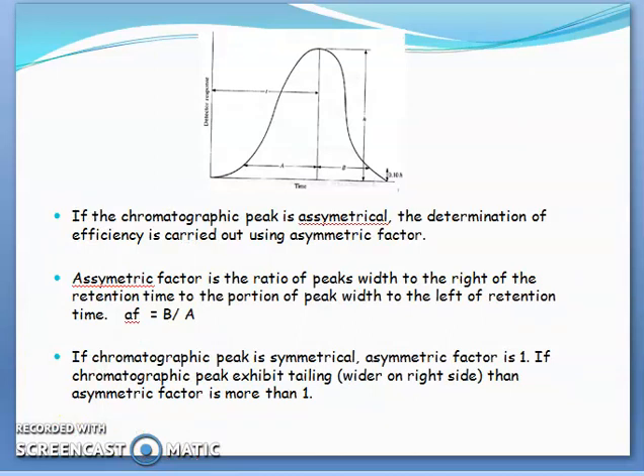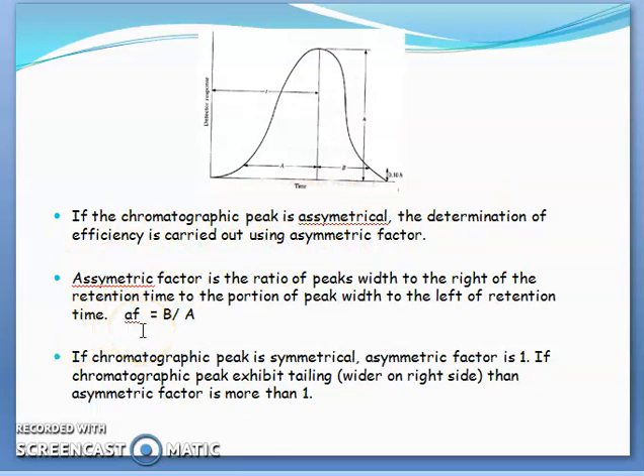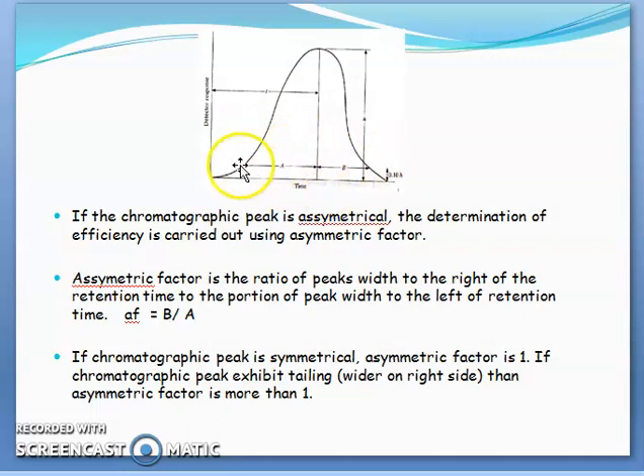For an asymmetric peak, the efficiency is determined using the asymmetric factor AF. The asymmetric factor AF equals B/A, which is the ratio of peak width to the right of the retention time (B) to the peak width to the left of the retention time (A). If the peak is symmetrical, the asymmetric factor is 1. But if the peak exhibits tailing or fronting, the asymmetric factor may vary from 1.